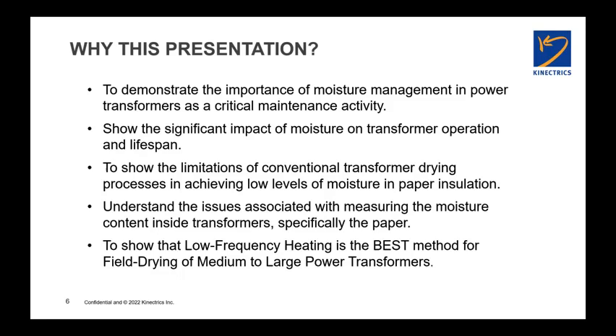And you're going to hear a lot from me in the next 40–45 minutes talking about paper insulation versus oil insulation. And we know in an oil filled transformer, which is what this topic focuses on, the insulation system, quote unquote, is comprised of the paper and the oil together. They work hand in glove to provide the insulation inside the tank.